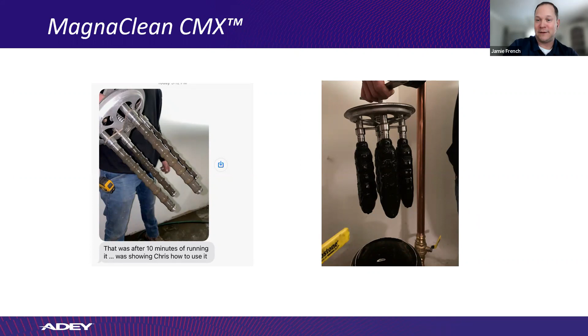I need to mention our chemicals because they're just as important as our filters. What we have available in North America right now is MC1, our protector, and MC3, our cleaner. Something we offer that other chemical manufacturers do not is what we call compensation chemistry, where the cleaner has a little bit of inhibitor in it. So it can stay in a system up to 28 days. If it starts uncovering and leaving bare metal behind, it'll actually apply a little bit of inhibitor there until you drain it down, fill it back up, and put your inhibitor in, which has a little bit of compensation chemistry to be able to neutralize up to 20% of the cleaner left.